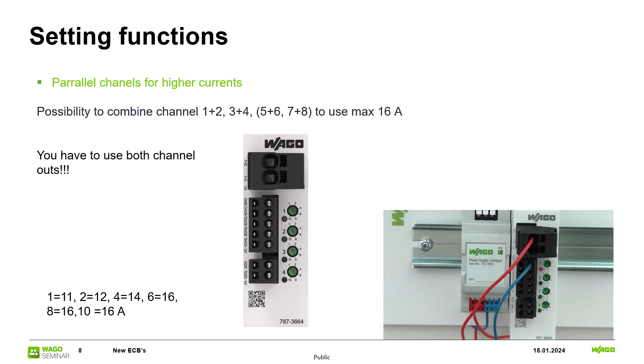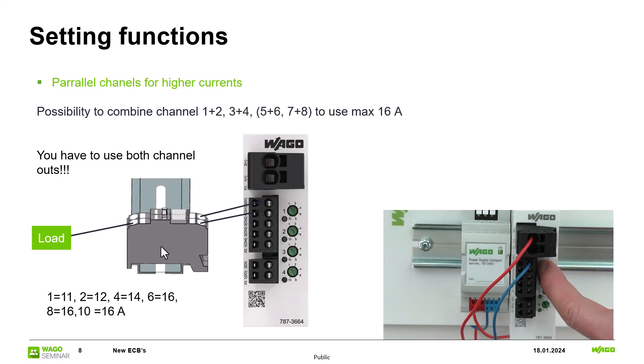Important to know is that you have to use both channel outputs. So please go with the conductor to a terminal block where the jumper is located and then go with only one conductor to your load. If you press channel number 1 again for at least 3 seconds you deactivate the parallel mode and you can activate the channels by yourself again.